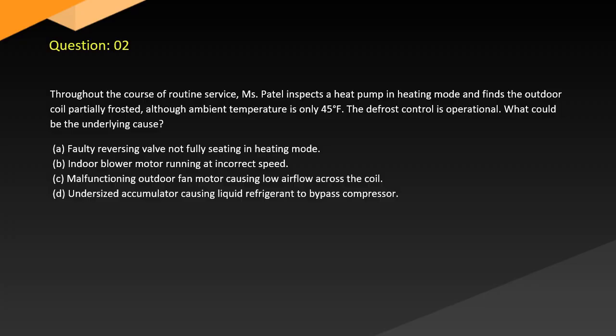Question 2. Throughout the course of routine services, Patel inspects a heat pump in heating mode and finds the outdoor coil partially frosted, although ambient temperature is only 45 degrees. The defrost control is operational. What could be the underlying cause?